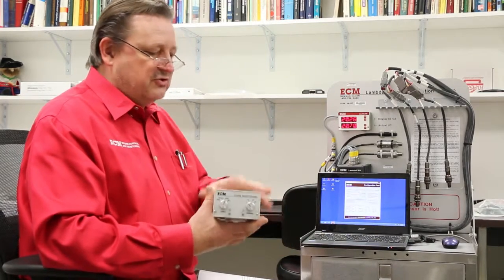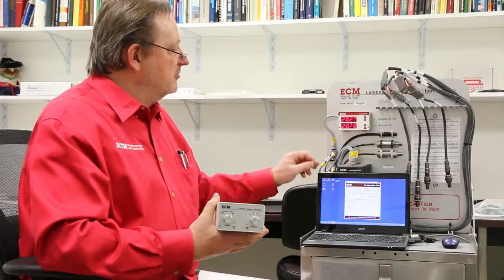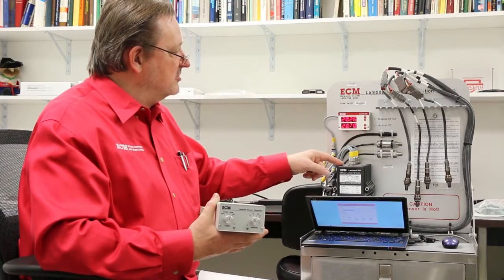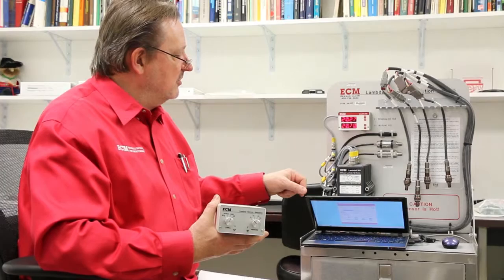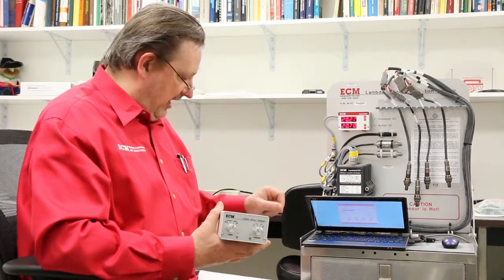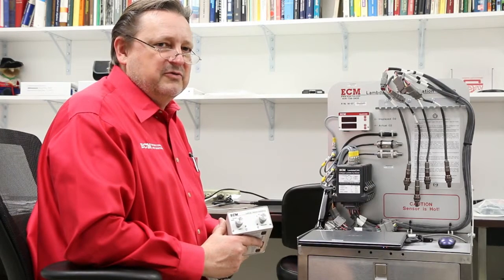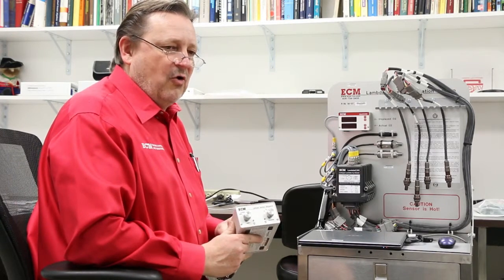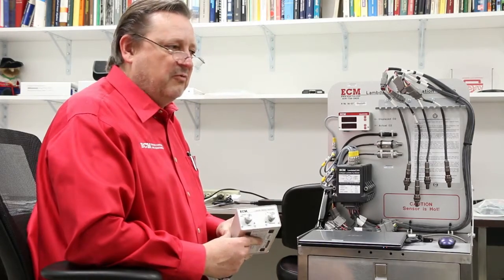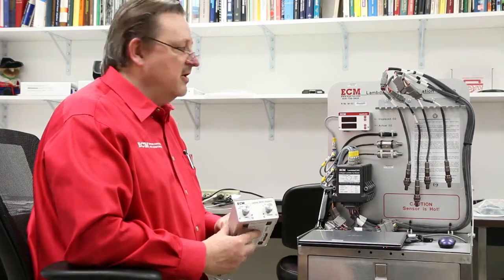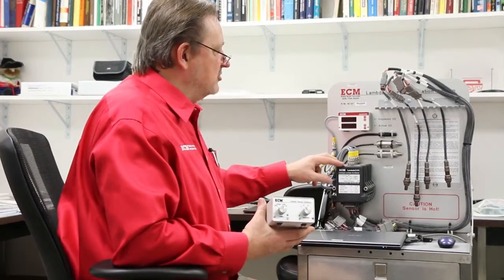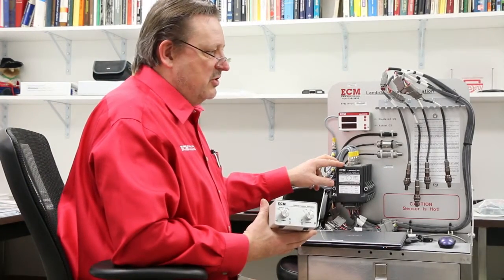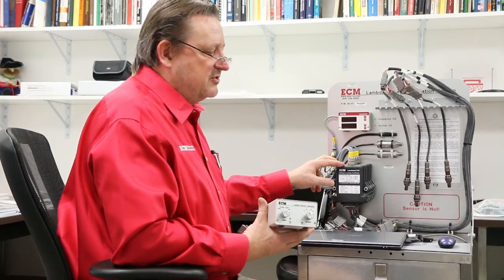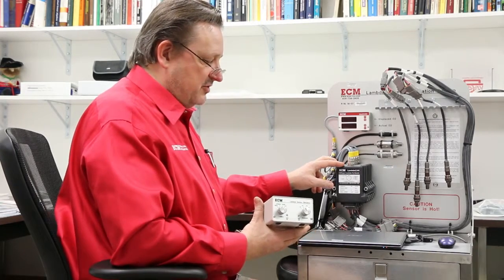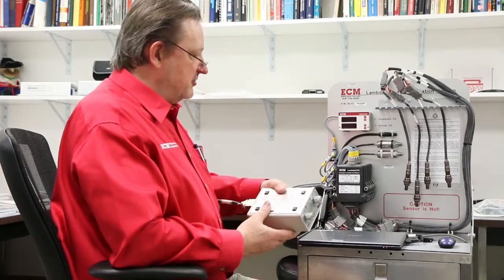We recommend that you use this sensor simulator to check the ability of these 4 modules, the Lambda CAN modules, to properly measure current and voltage. Now I'm going to explain how to use this Lambda O2 sensor simulator, which also simulates the pressure sensor. And you use it to check the ability of these 4 Lambda CAN modules to measure the current from the Lambda sensor and the voltage from the pressure sensor. You follow the instructions on the back.